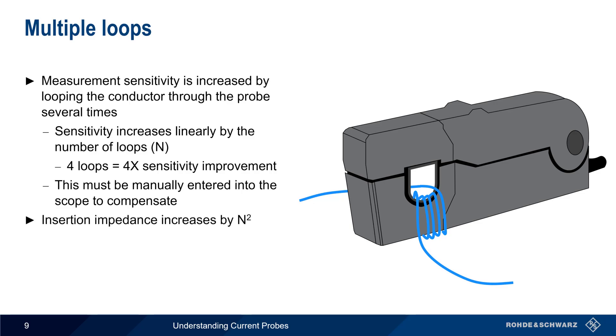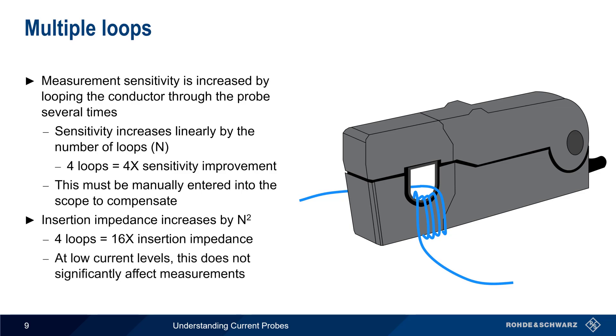These loops also increase the insertion impedance by the square of the number of loops — so four loops would increase the insertion impedance by a factor of 16. However, this increased insertion impedance is usually quite small and does not significantly affect measurements at low current levels.